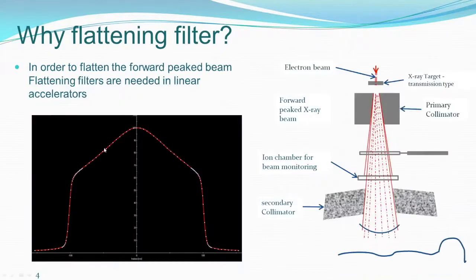For example, this is the profile you now get for any FFF beam, right? It's quite interesting to see, which we studied theoretically with the H.E. Johns book earlier. When you don't have a flattening filter, your beam is more forward peaked. And in those days, the idea was to give a uniform dose distribution, so one would like to have a uniform beam profile. So they decided to flatten this profile and introduced a flattening filter.